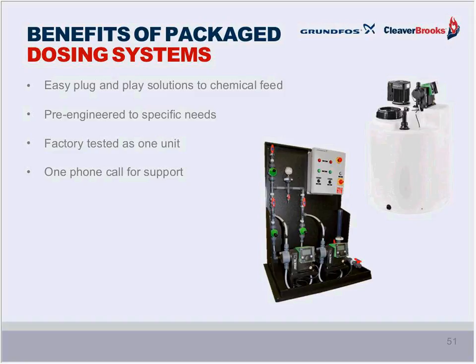The dosing systems come integrated and allow all components to function properly together as an integrated system. Second, it is best to install a system with 2 or more pumps for duty standby operation. This allows treatment to continue when pump maintenance is necessary, and the system allows this to be done easily.